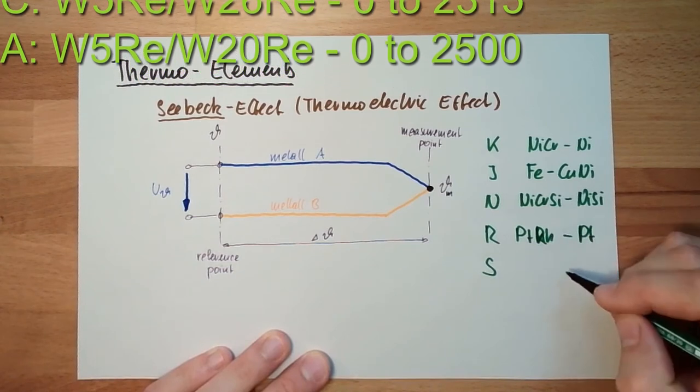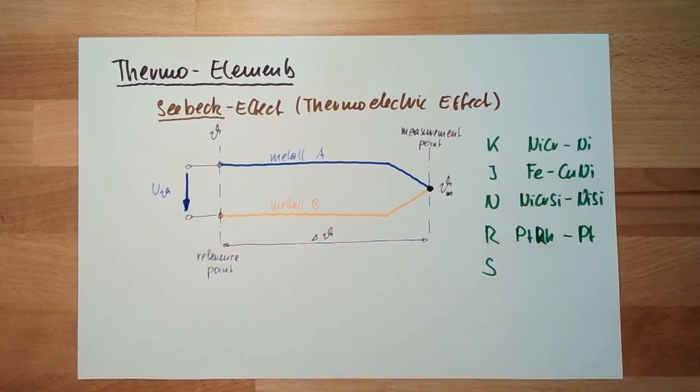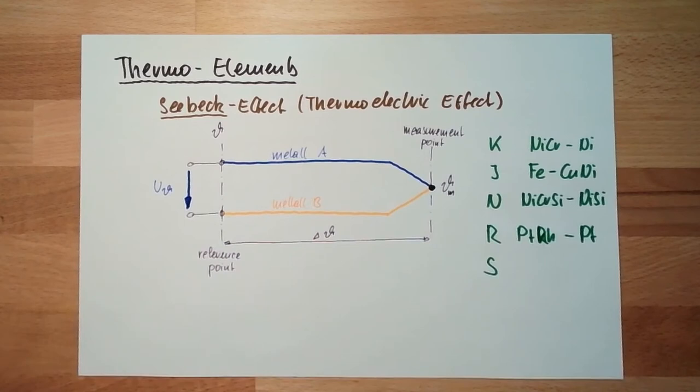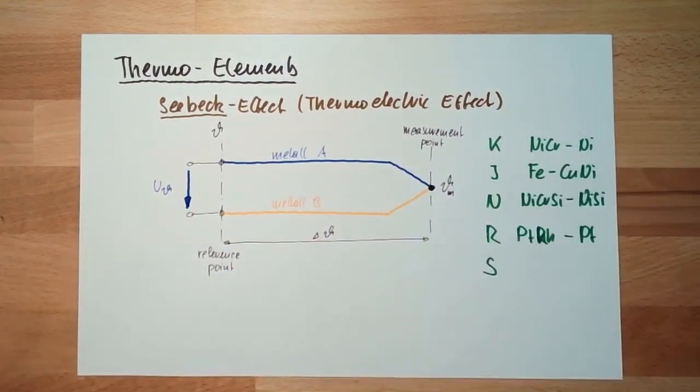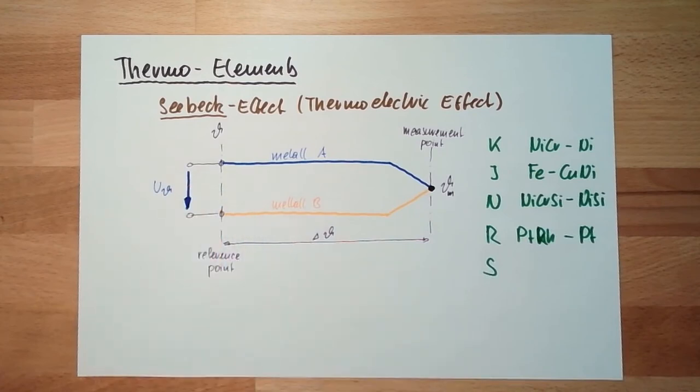These are the most common ones - K, J, and N. But there is also platinum, so there is type R and type S - platinum-rhodium, rhodium-platinum. There are different types, they are defined differently. In your script, you have a list of them. You don't need to know this from the top of your head, but please keep in mind there are different types of thermoelements, and you have to select one according to your temperature range. So that's one thing - the metal combination.